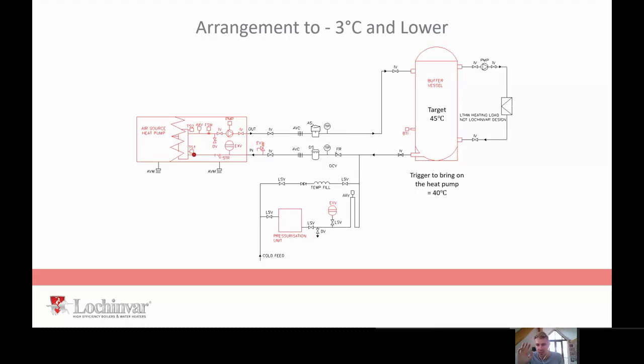So if you've worked with gas boilers in the past, they're going to work on a 20. They're working at 80, 60, right? Well, this can only work on a 5-degree delta T. It's a much faster flow rate. So a 45 kilowatt boiler with a 20-degree delta T would require a quarter of the flow rate a heat pump would require because it's got that tighter delta T. So for the same heat transfer, you need to flow 4 times faster.